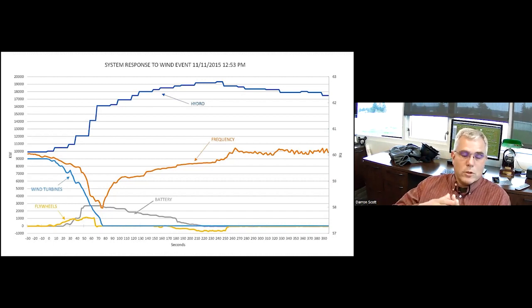The batteries, on the other hand, can go 15 minutes at full load for 3 megawatts. That's the strength of batteries, but the weakness is every time you hit them, you lose a little bit. The strength of flywheels is you can hit them a lot, but they don't have much energy. So we try to marry the two and let each cover the other's weaknesses, which has been a pretty good way to do it.